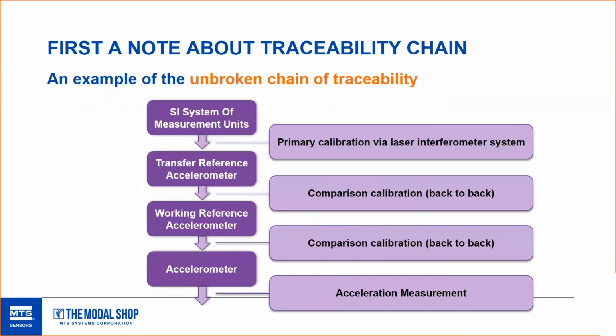But really, the note about traceability: what you're looking for is an unbroken chain of traceability from your measurement to a primary source, the base units. Your sensor may follow a similar path, but the unbroken chain to a primary source is usually very important for lab grade measurement. And then let's talk again real quick on the topic of field calibration. Calibration is a pretty funny word.